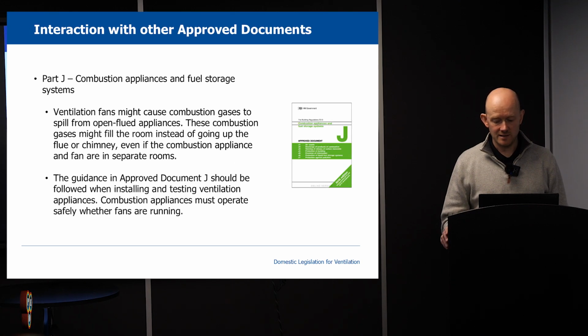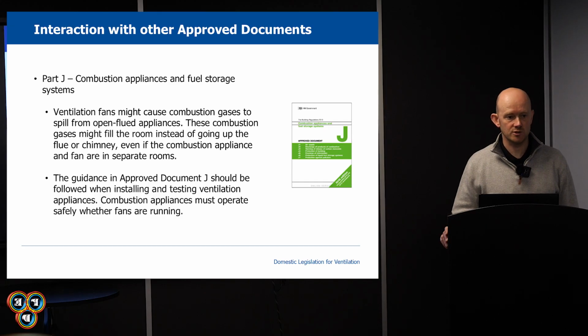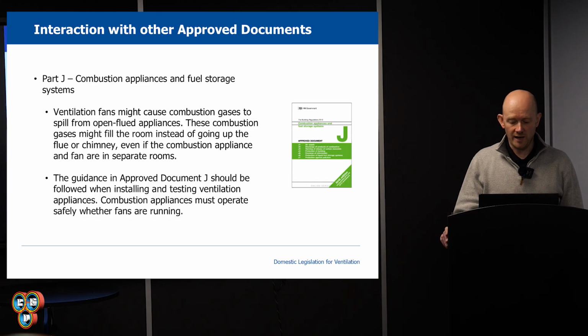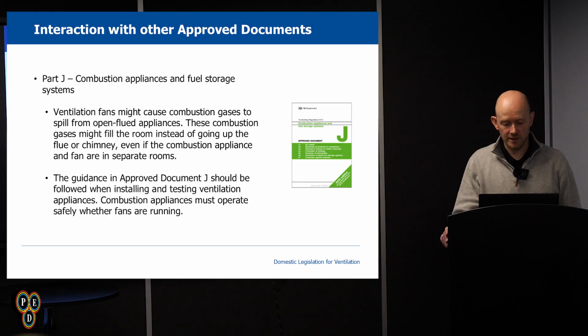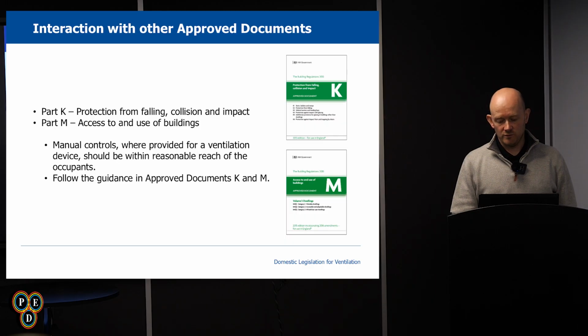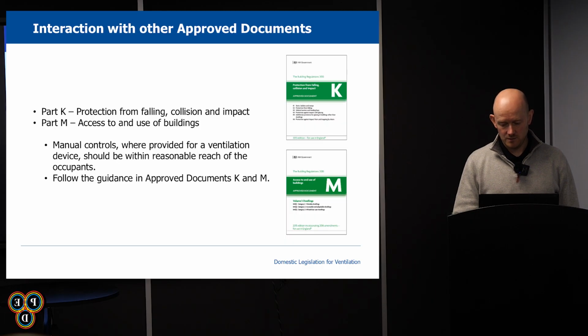Interaction with Part J, combustion appliances and fuel storage systems. Part F cannot supersede Part J. Permanently open air vents are required for combustion, as ventilation fans might cause combustion gases to spill from open flued appliances. Interaction with Parts K and M, which cover protection from falling, access and the use of buildings, which states that controls should be within reasonable reach of occupants.